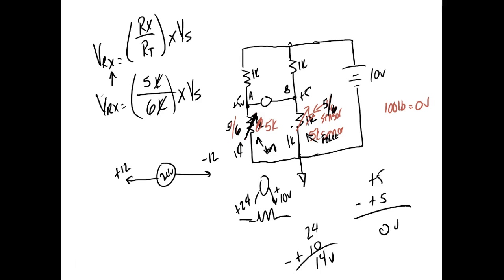So we take the combination of this and call this a load cell. The load cell has 2 voltages we call excitation voltage, and then we get an output that comes into our scale. We get 2 wires coming out, so every load cell has 4 wires total, with the bridge built into the load cell. 2 of them are where you put your excitation voltage, usually 10 to 15 volts, and the other 2 are the actual differential output. That comes into our scale, and then we zero the indicator. So we don't set 0 on the bridge.